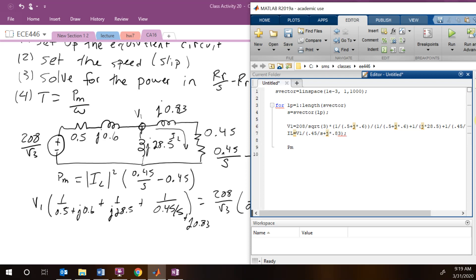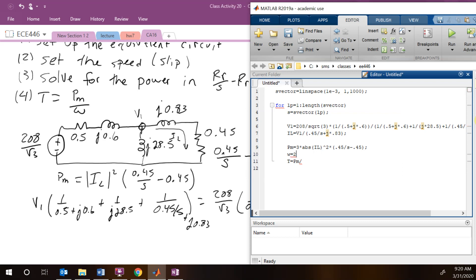Our mechanical power is going to be 3, because we have three phases, times the magnitude of IL squared, times only the resistance corresponding to mechanical power: 0.45 divided by s minus 0.45. Then torque is equal to P_mechanical divided by omega, where omega is 2 times pi times 60 times (1 minus s).